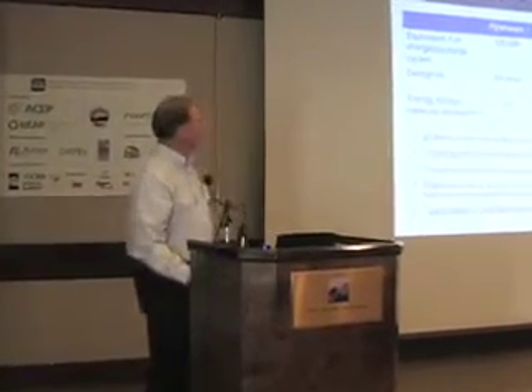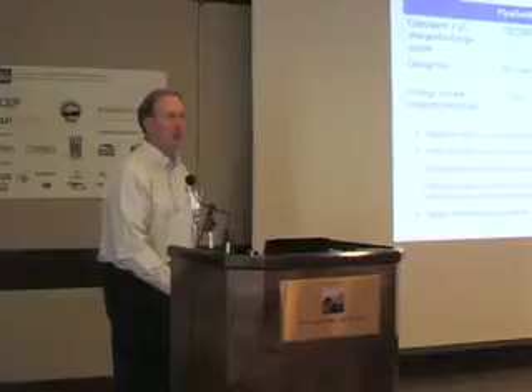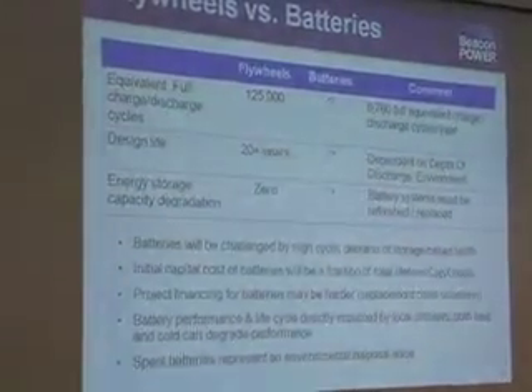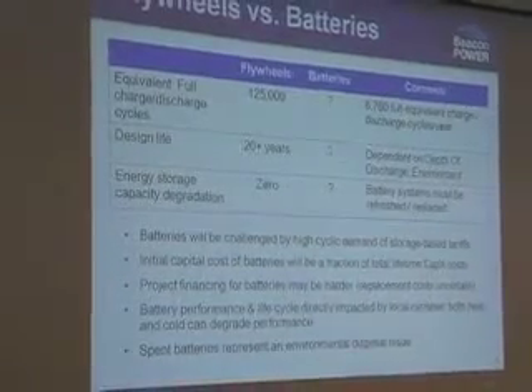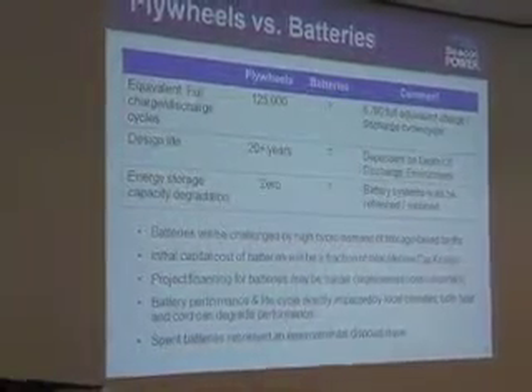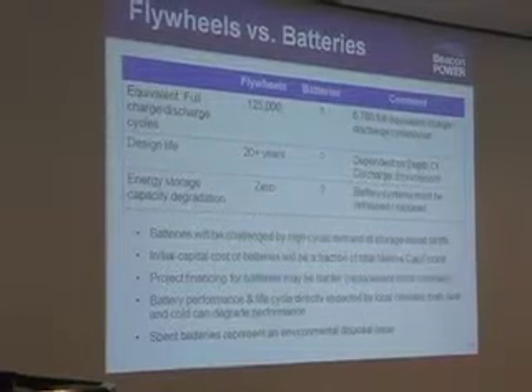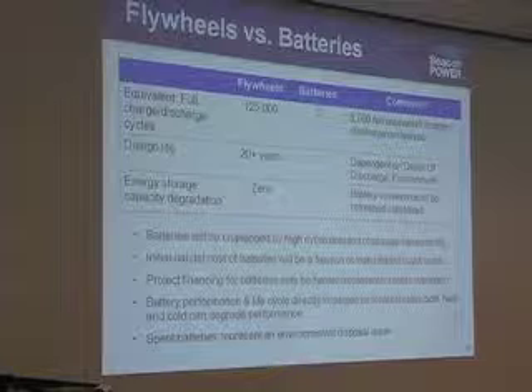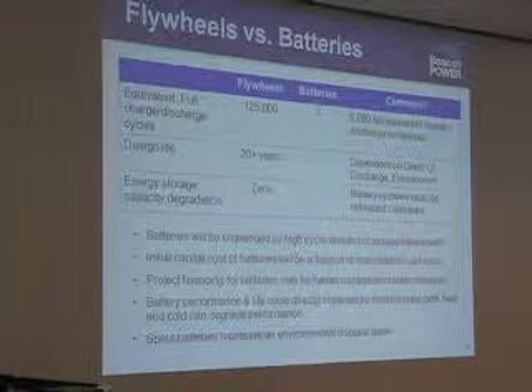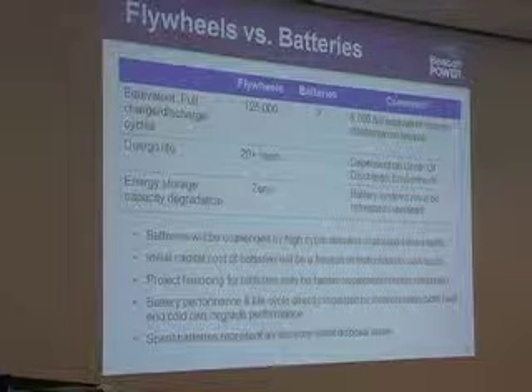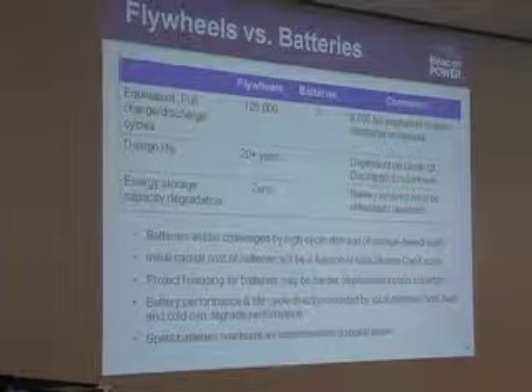All right, just a couple of topics in terms of how flywheels and batteries differentiate. Probably the biggest differentiator is that the flywheels themselves really don't care how many full charge discharge cycles they do. We do over 8,700 full charge discharge cycles already. Over a 20-year lifespan, that's 125,000 to 150,000 cycles. Like I say, they don't care, they're spinning, and they just do work.